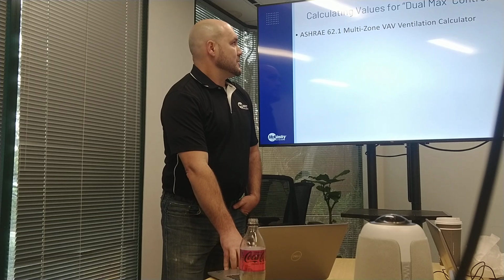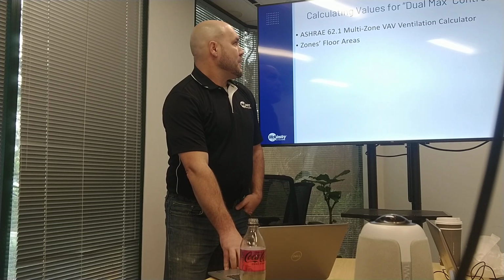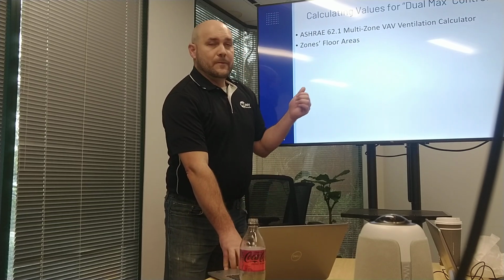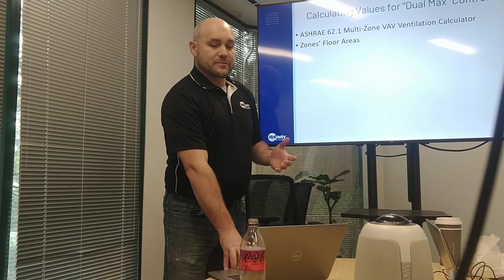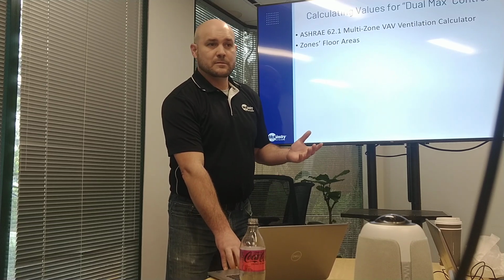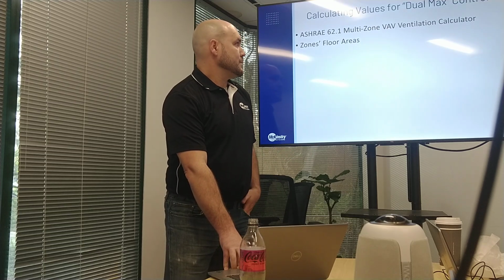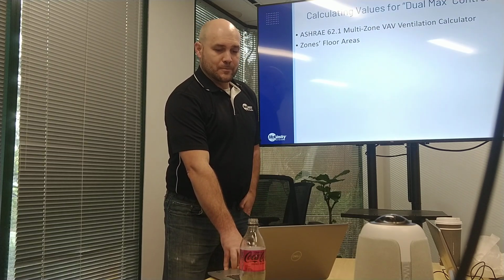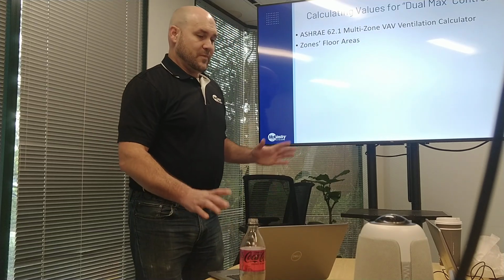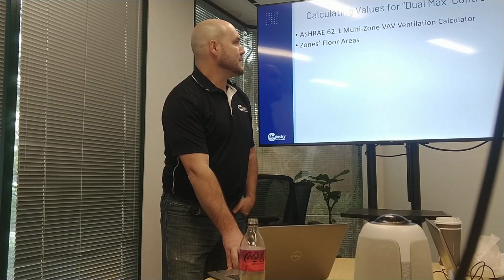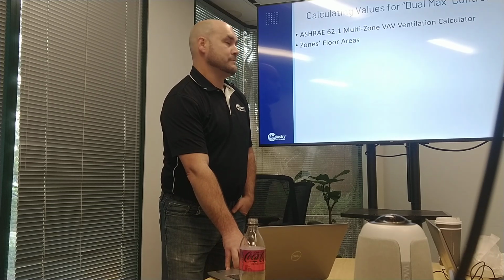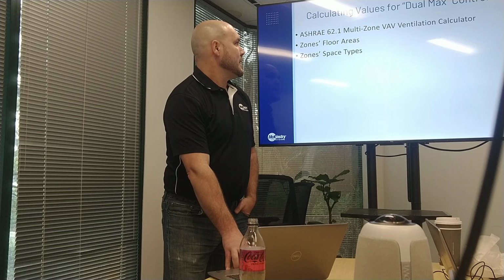So how do you calculate these values for dual max control? You use the multi-zone VAV ventilation calculator for all those that had the green asterisk. That requires knowledge or takeoffs of the floor areas of the zones, which is a tedious thing to do, admittedly, but that's a required input. So if the client has zone areas known, fantastic. If they have clean, scalable PDFs of their drawings of their building, okay, we can do the legwork and do those takeoffs.